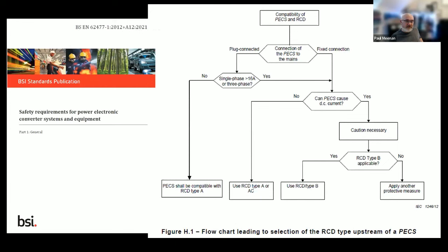Well, that's interesting. So if it's plug connected and greater than 16 ampere three phase, then we ask, does it cause a DC current? And if it does, we take cautions, and then potentially we apply a type B RCD. And if that won't work, we then apply another protective measure. But if we have plug connected and less than 16 amp, then we're recommending type A compatibility.